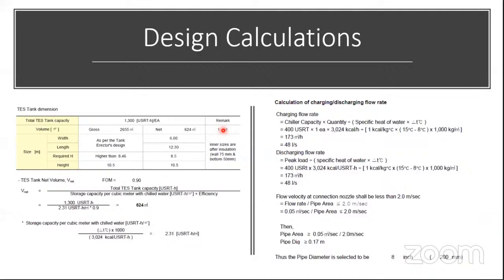The tanks can be rectangular. Here it was a rectangular tank, an RCC tank to be precise. These tanks can also be MS, and sometimes they are cylindrical in construction. We'll also try to understand this term, figure of merit. This is the storage efficiency, which is applied for calculating the net volume of the thermal storage tank. Then there is also a calculation based on the peak flow across thermal storage, and the pipe size is also calculated, that is, the inlet outlet connection size of the stratified thermal storage tank.